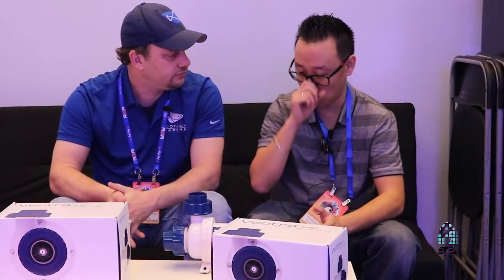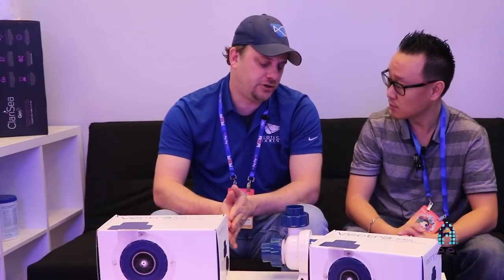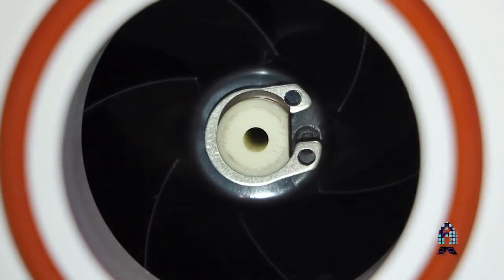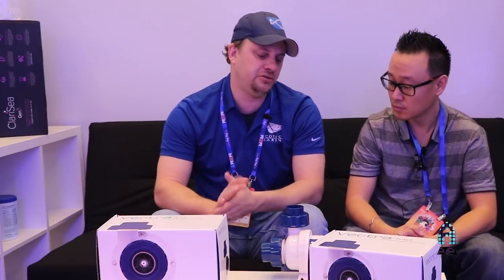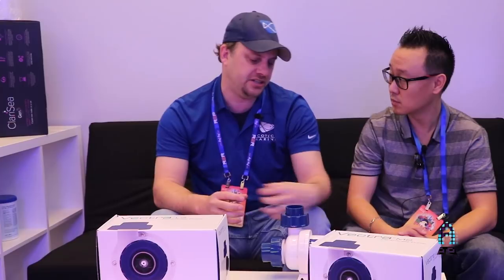I was also told this one has more protection against elements like high temperature. The Vectras incorporate a thermal liner — basically a plastic able to withstand higher heat — along with bearing clearances that allow the pump to operate freely. There are also cooling channels on some models to keep the bearings cool while the pump is operating, and all of that takes place inside the motor housing.